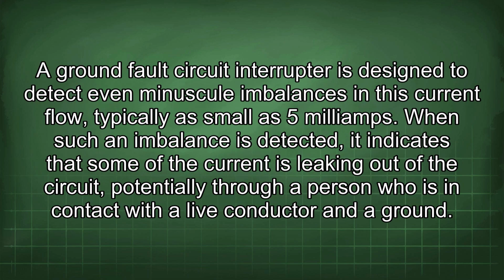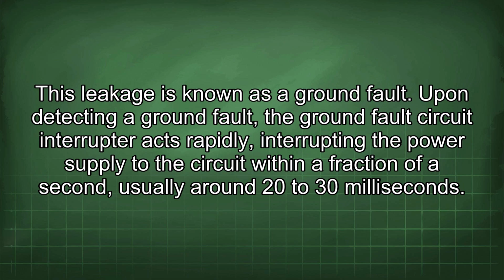A ground fault circuit interrupter is designed to detect even minuscule imbalances in this current flow, typically as small as 5 mA. When such an imbalance is detected, it indicates that some of the current is leaking out of the circuit, potentially through a person who is in contact with a live conductor and a ground. This leakage is known as a ground fault. Upon detecting a ground fault, the ground fault circuit interrupter acts rapidly, interrupting the power supply to the circuit within a fraction of a second, usually around 20 to 30 milliseconds.